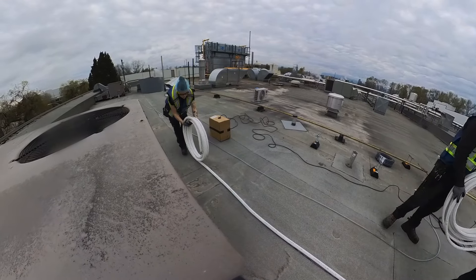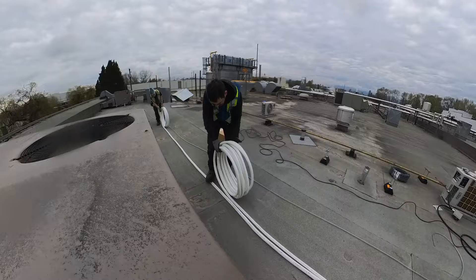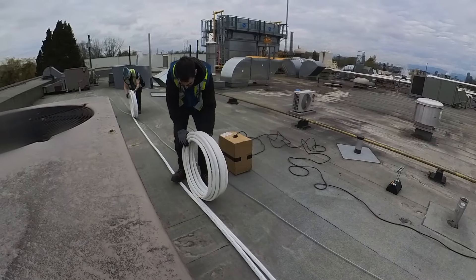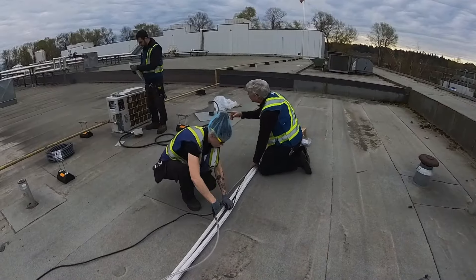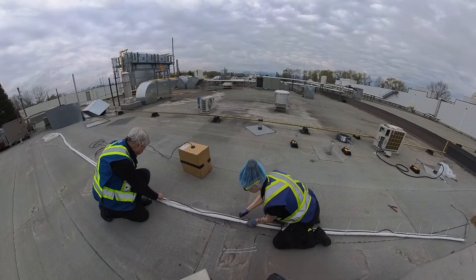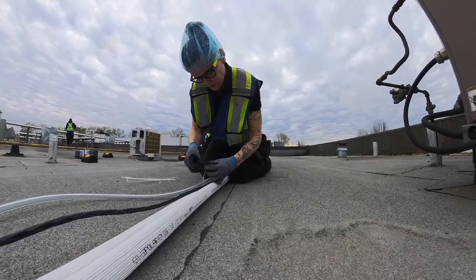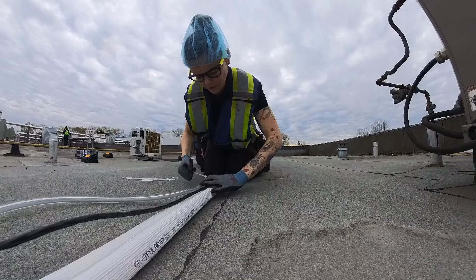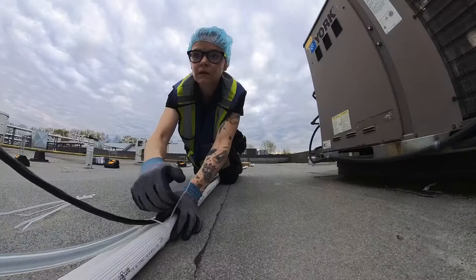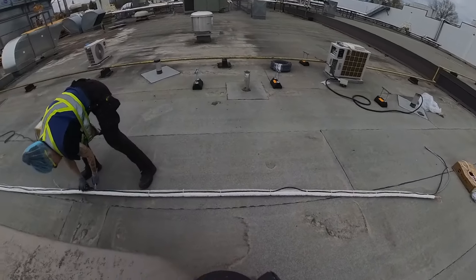We have a strategy when it comes to installing these ductless splits with our line sets. We're carefully unrolling these line sets — we've got a quarter and a three-eight here covered in insulation. What we usually do is roll everything out together. Luckily here on the roof we've got lots of space to work with. We roll that out together, put it with the drain line and also with the control cable, so it's just a little bundle of four. Then we zap strap those together, strapping them all nicely so they don't come loose. And we're going to send this down through the roof jack all in one piece. Just snipping off the tails of those zap straps so it's nice and neat. Now we have one long line set, all ready to go. Saves us a bunch of time and energy.